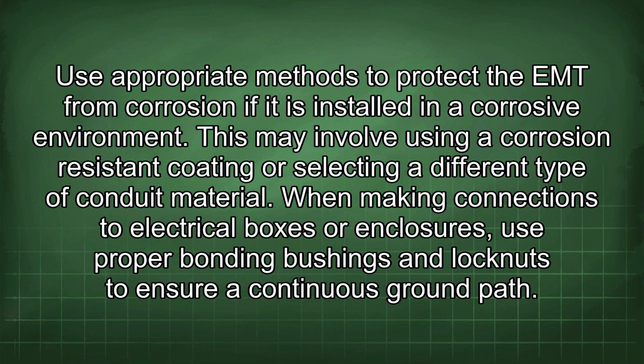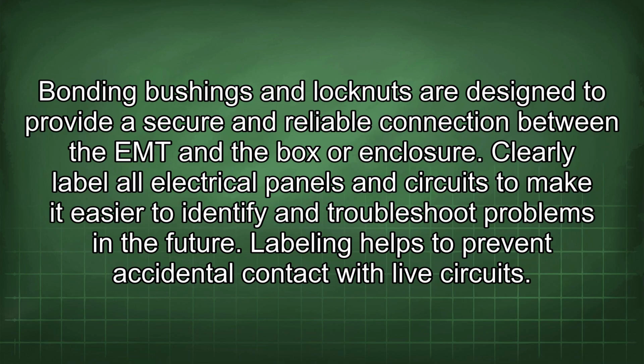When making connections to electrical boxes or enclosures, use proper bonding bushings and lock nuts to ensure a continuous ground path. Bonding bushings and lock nuts are designed to provide a secure and reliable connection between the EMT and the box or enclosure. Clearly label all electrical panels and circuits to make it easier to identify and troubleshoot problems in the future. Labeling helps to prevent accidental contact with live circuits.